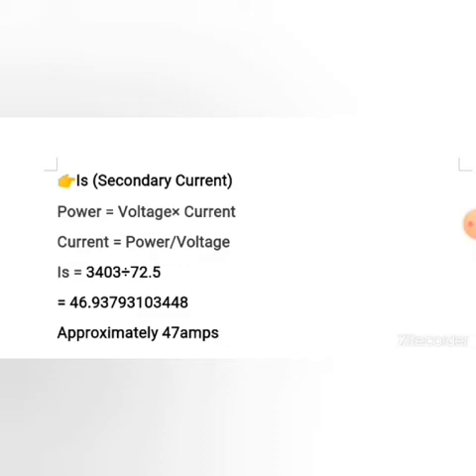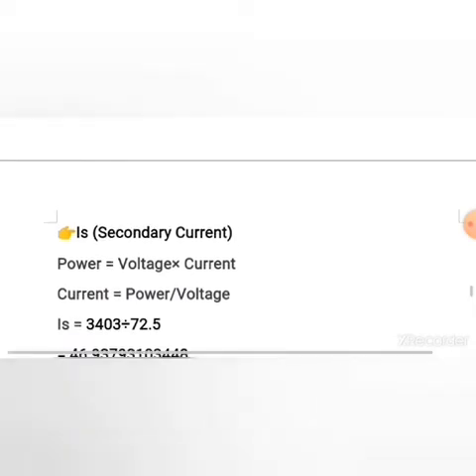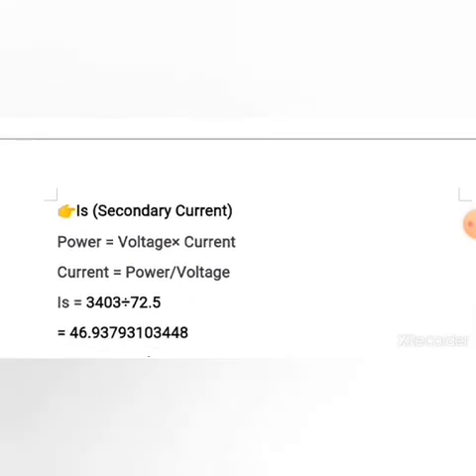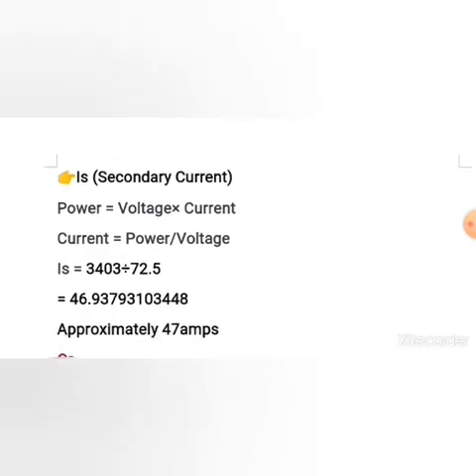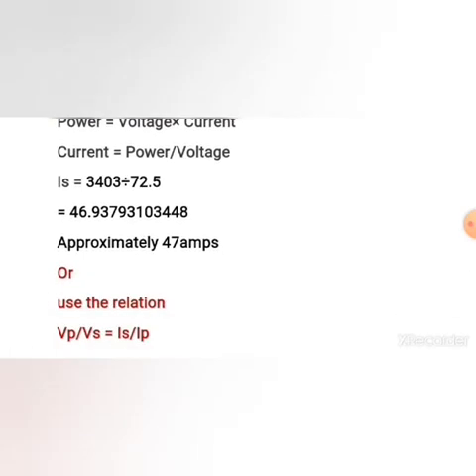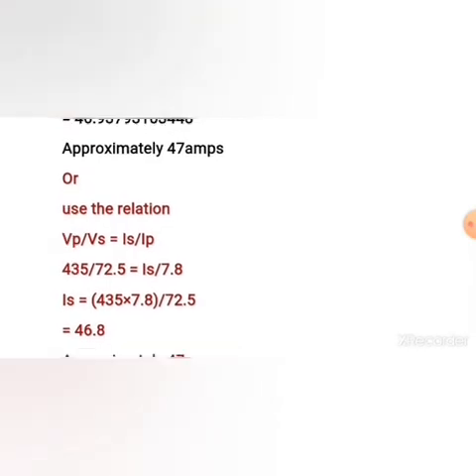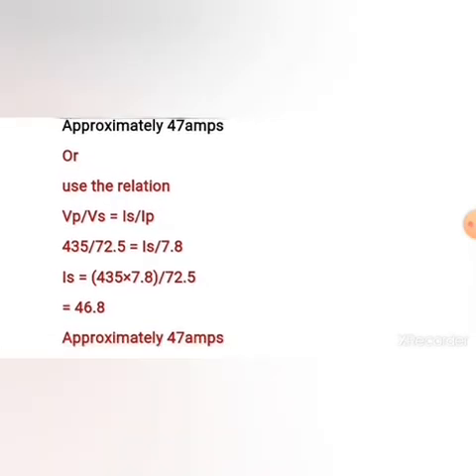At maximum conditions of this welding transformer: maximum power is 3,403 watts, maximum input voltage is 435 volts, and maximum primary current is 7.8 amps. At these maximum conditions, you must get 47 amps and 72.5 volts at your secondary side. You can also use the popular transformer current formula — substituting primary turns, secondary turns, and primary current — and you will still get approximately 47 amps at the secondary. You can verify these calculations yourself.